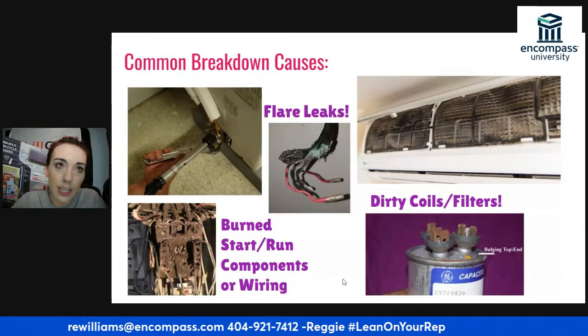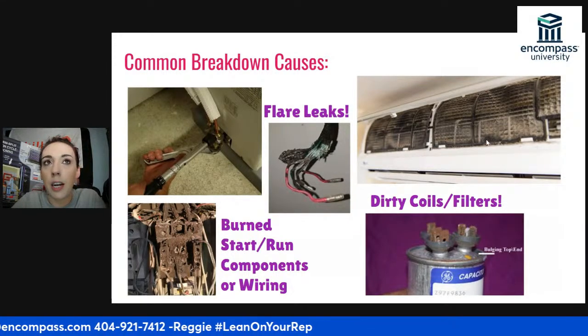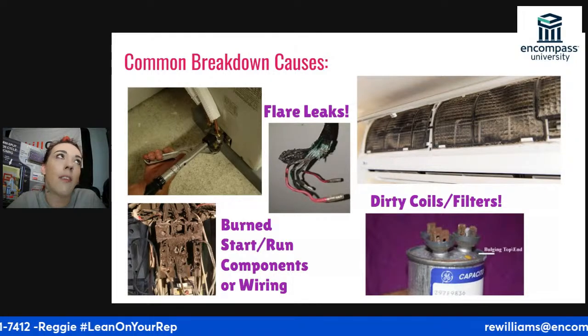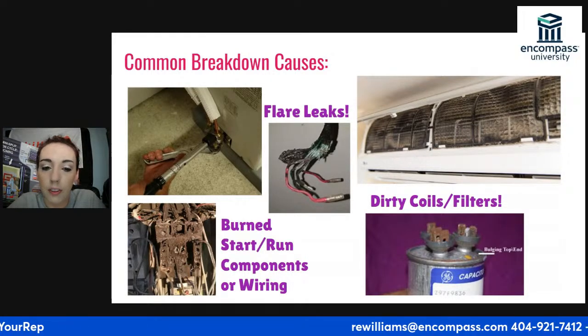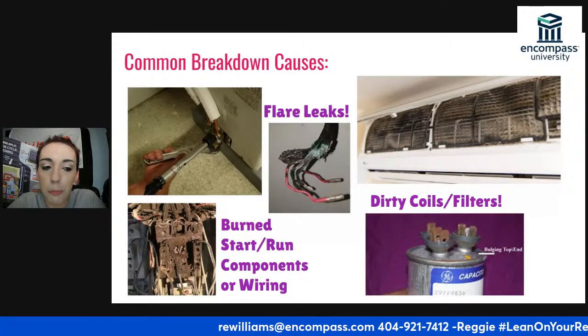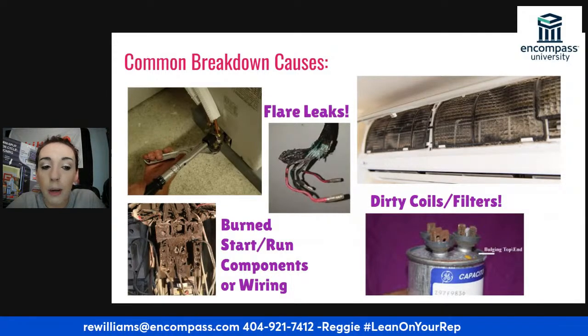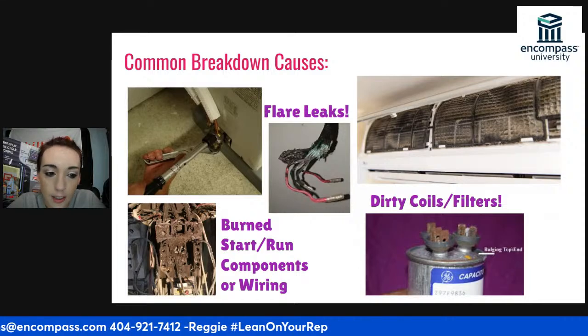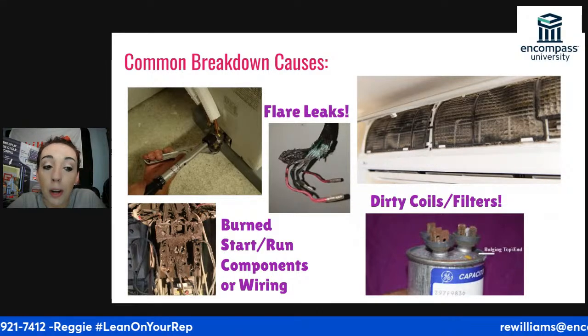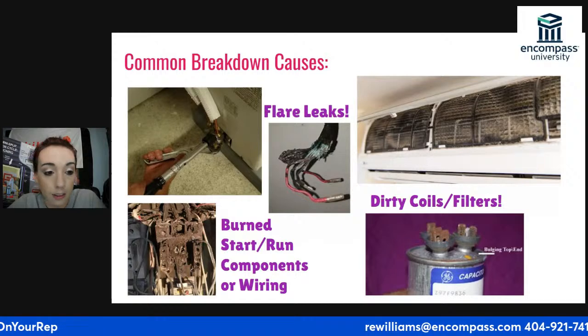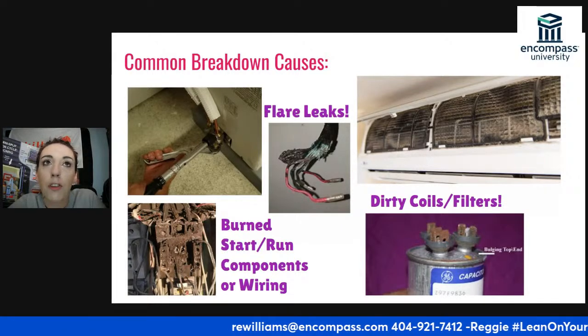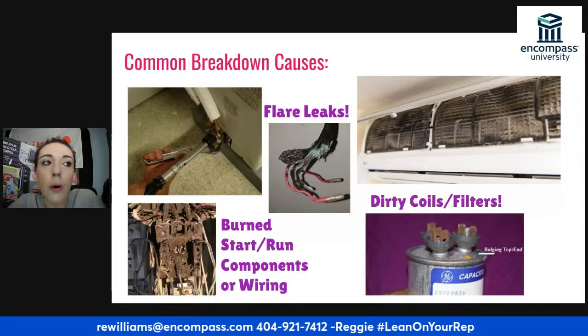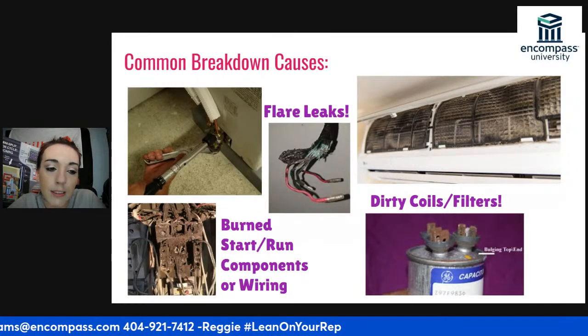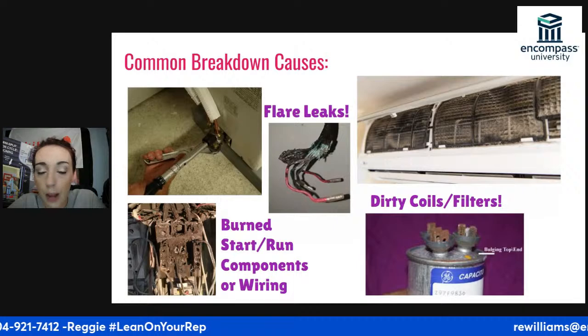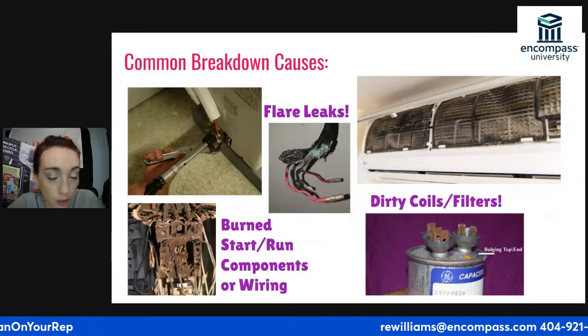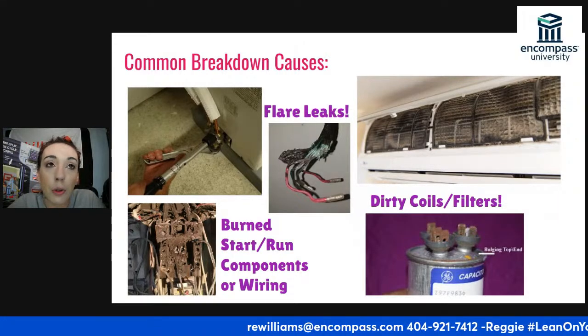And then the next thing, obviously, I'll touch on the dirty coils and filters. We did talk about that a little bit, but I can't even express how often this is the problem. Almost every single mini split I've ever been called to on a no cool call, whether it was the reason it wasn't cooling or not, was dirty. When you hook up your probes or your gauges, your manifolds, analogs, doesn't matter, you are not going to get correct temperature and pressure readings if your system is dirty. So regardless of why you have a no cool call, you need to make sure that these units are clean.